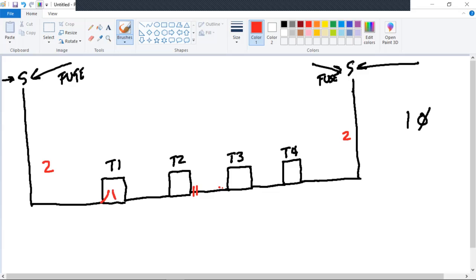So in A, out. A stood off. B still coming in here, but it's not going to the bushing of the transformer. This side over here, in A, out B. In A, out B. And once again, we're coming down here and dead-ending and standing off. So this is pretty simple to understand. If I'm going from left to right, in, out, in, out. Remember on your transformers, if you're coming from right to left with the feed, this direction is still in A, but it's out B and it crosses like that. So don't let anything like that confuse you.